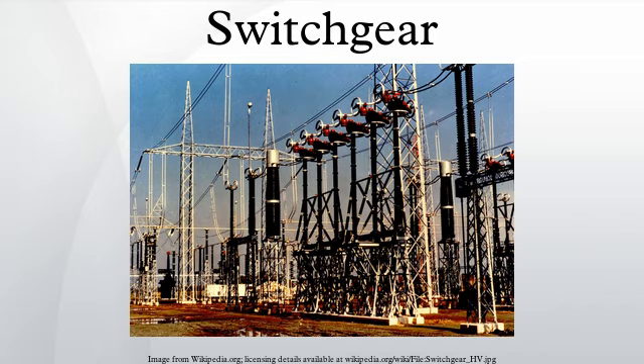Safety: to help ensure safe operation sequences of switchgear, trapped key interlocking provides predefined scenarios of operation. For example, if only one of two sources of supply is permitted to be connected at a given time, the interlock scheme may require that the first switch must be opened to release a key that will allow closing the second switch. Complex schemes are possible. Indoor switchgear can also be type tested for internal arc containment. This test is important for user safety as modern switchgear is capable of switching large currents.